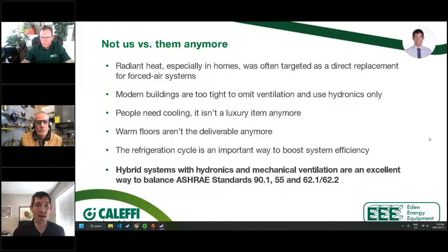But I think that the hybrid systems that we can build with the best of both are the future of addressing these sensible and latent loads the most effective way, and leveraging air moving around for its strength, which is dealing with humidity, lowering the latent loads. And then hydronics is really great at the sensible loads. And we can combine those two to make a really ideal system that we could move to a zero energy future with.